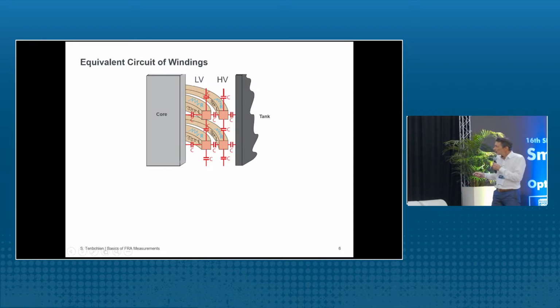If we have, for example, two windings, a low voltage winding and a high voltage winding, then of course these windings have inductance, also resistance, and these windings have capacitance to the other winding, also to the transformer tank, to the core. So it is more or less an LCR circuit.